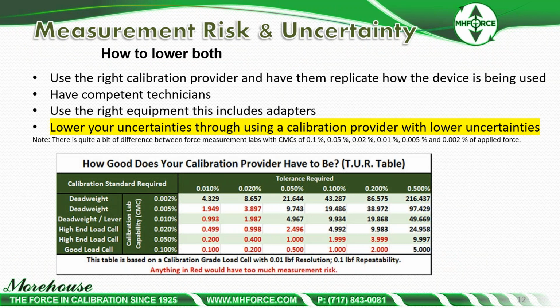So when you start looking at risk and uncertainty and you start looking at how to lower them, one of the main things you want to do is use the right calibration provider and have them replicate how the device is being used, have competent technicians, use the right equipment that includes adapters. There's a paper we wrote on adapters, very, very critical. One adapter, you could tell us you want a 0.05% accuracy, and if you're changing adapters, you could have an additional error of 0.3%. So that 0.05% means nothing if you're changing adapters and have a 0.3% error on those adapters. And then you can lower your uncertainties through using a calibration provider with lower uncertainties. That's really tolerance required. This table here is saying how much risk, the tolerance required, where do you need to go. Anything in red would have too much measurement risk.